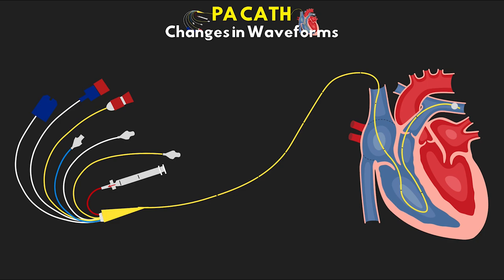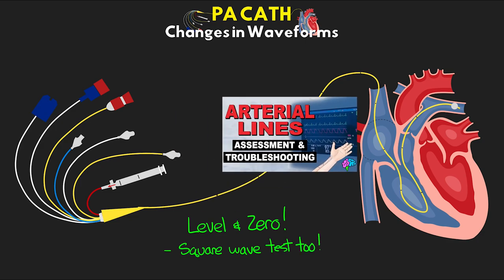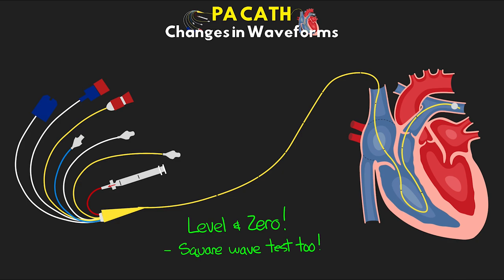Quickly, I want to hit on leveling and zeroing, because you always want to make sure you are leveled and zeroed to know that the numbers and waveforms you're looking at are actually correct. We need to be doing that square wave test to ensure proper dampening. I'm going to link to a lesson where I talked about this more in depth when discussing arterial lines, but it's still very applicable here.